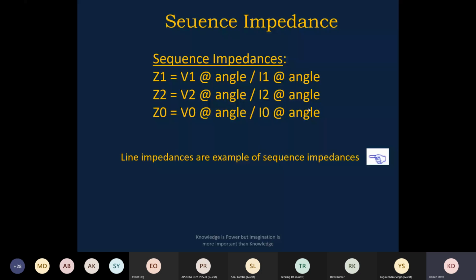Some manufacturers calculate Z0 by Z1 in the relay. Some manufacturers calculate Z0 minus Z1 divided by 3Z1. Some manufacturers calculate R0 minus R1 divided by 3R1 plus jX0 minus X1 divided by 3X1. That is the R plus jX form, the rectangular form of the residual compensation factor. So that is how we use Z1, Z2, Z0: Z1 is the positive sequence impedance, Z2 is the negative sequence impedance, and Z0 is the zero sequence impedance.